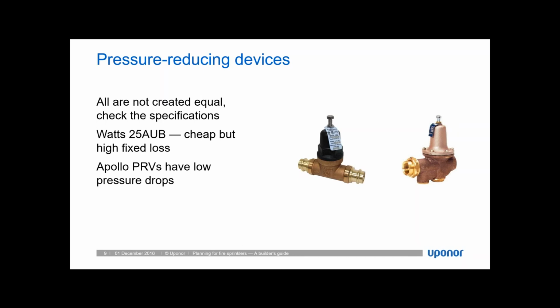If there are pressure reducing valves installed that the designer doesn't know about, there's going to be some pretty significant issues of the system design thinking that we have enough pressure, but in reality there's this huge amount of loss through a valve that your designer was not aware of, and this can cause some issues when you're trying to verify your system performance.